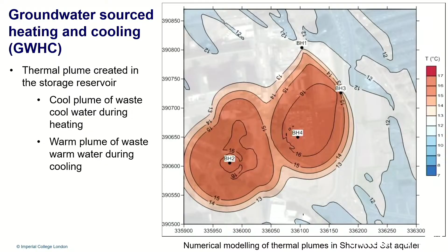Now we can operate this system in a different way, using the same or very similar infrastructure. When we want to provide heating, we abstract groundwater, pass it through our heat exchanger, and inject the cool waste. When we want to provide cooling, we switch the system around, producing from the borehole where we injected that cool water, and we get back the cool water we stored there.